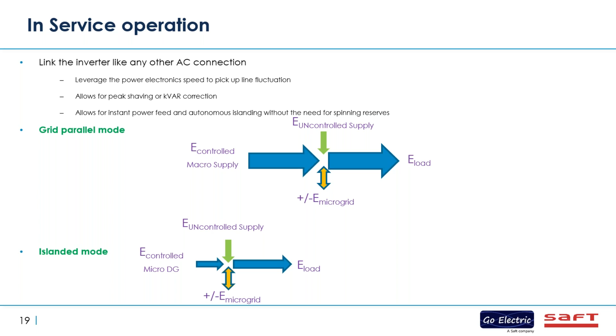This chart shows a transition between states where you have the grid present and you're running along in parallel operation, and then you have a grid loss. So with 4-quadrant power operation, your positive and negative real power, and then leading and lagging VAR. The grid is analogous to an infinite inertia motor. You cannot change the fundamental frequency of the microgrid.